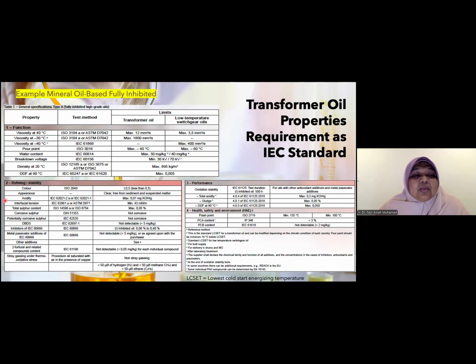Then we look at the acidity, appearance, and other requirements, such as the oxidation level of the material. Then in certain areas, the standard for lowest cold start energizing temperature is also an important factor, if the transformer is being used where we can find extreme cold weather. So this LCSET is a very important factor.